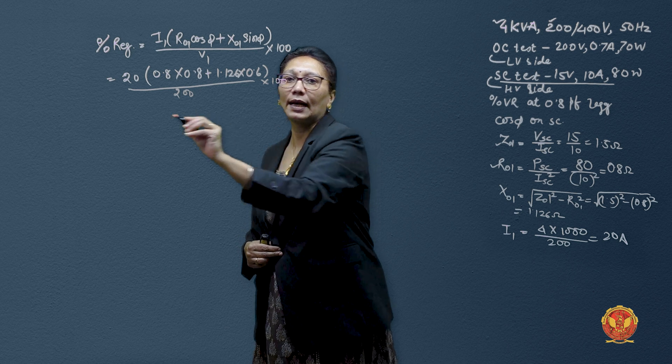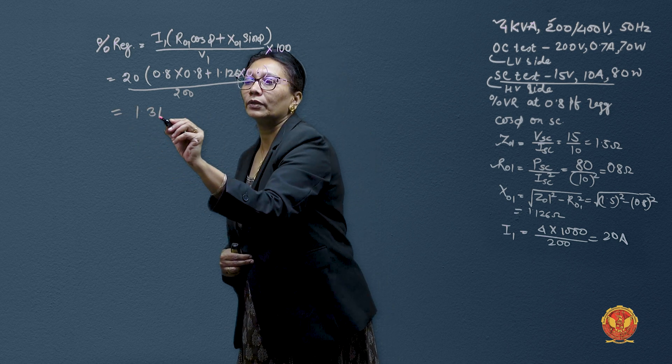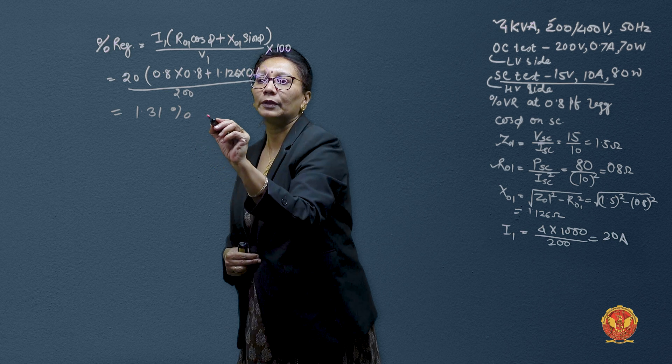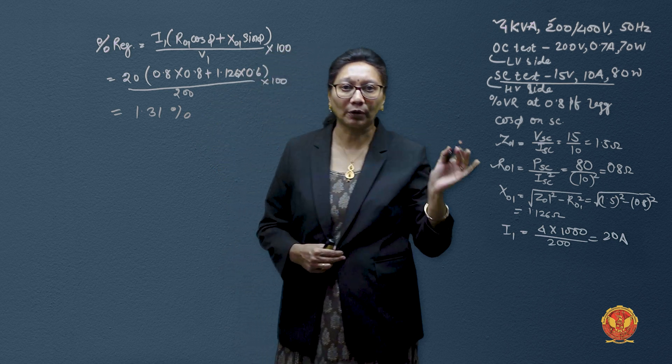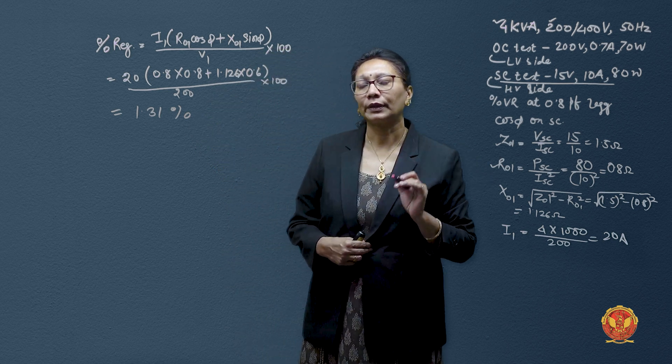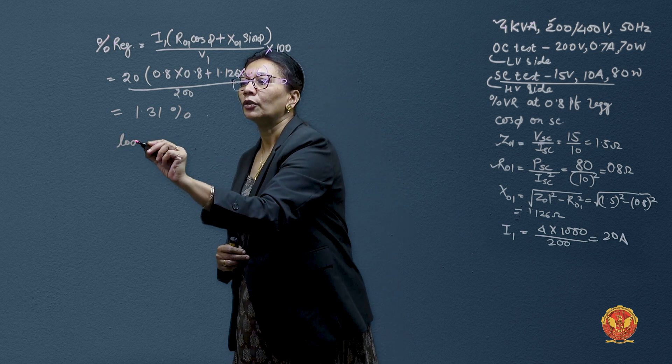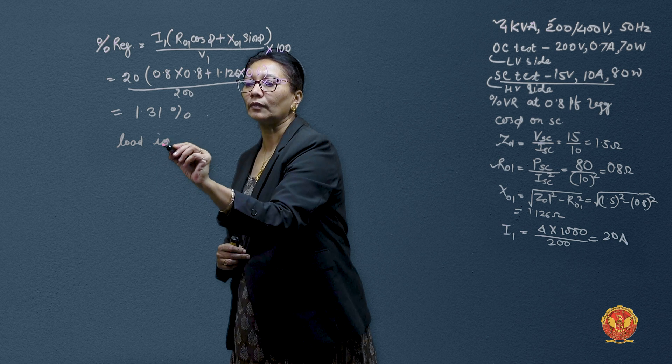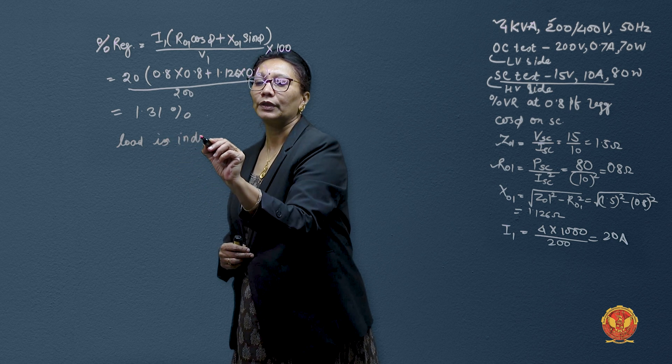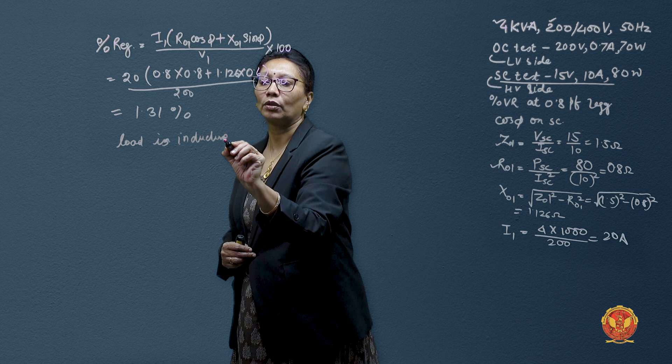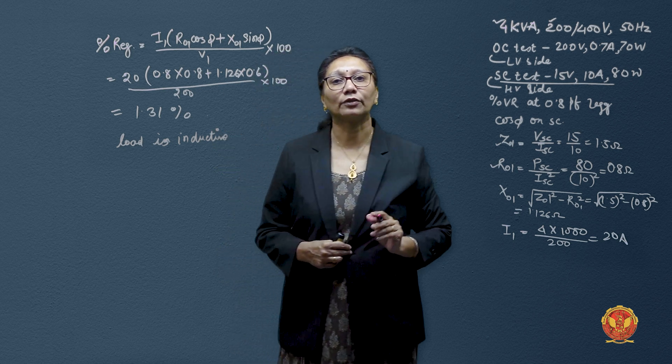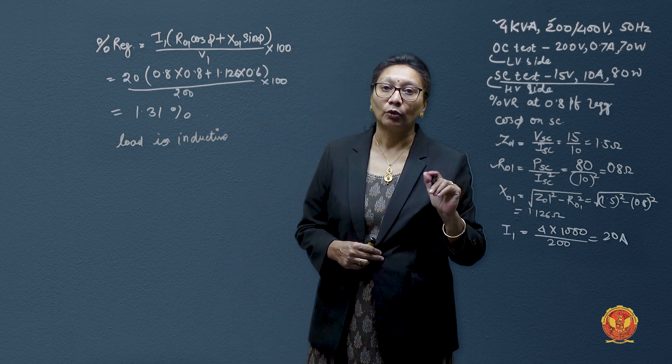So what is taken up and after calculation we obtain is 1.31% as it is coming as positive voltage regulation. We can conclude that load is lagging nature or inductive nature. So this is the case how we solve for voltage regulation with the case of short circuit and open circuit test.